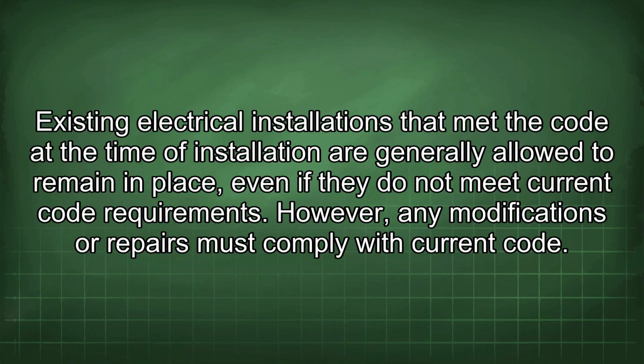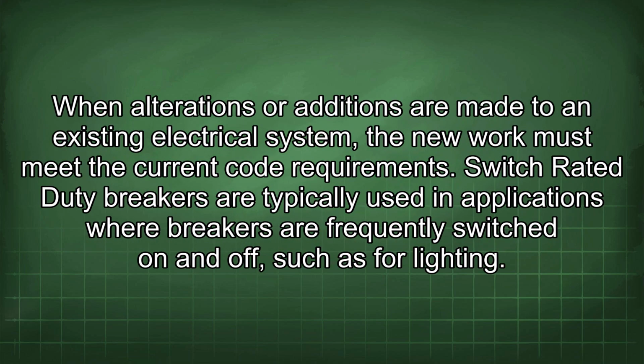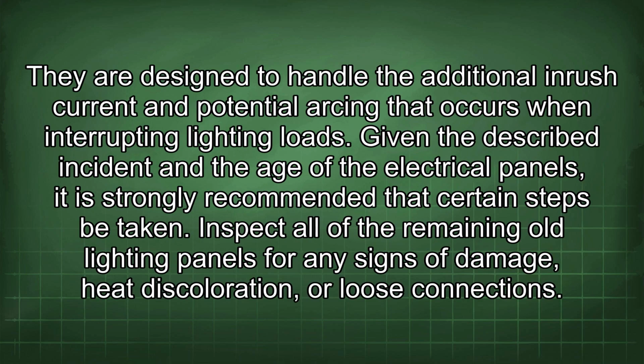Existing electrical installations that met the code at the time of installation are generally allowed to remain in place, even if they do not meet current code requirements. However, any modifications or repairs must comply with current code. When alterations or additions are made to an existing electrical system, the new work must meet the current code requirements. Switch-rated duty breakers are typically used in applications where breakers are frequently switched on and off, such as for lighting. They are designed to handle the additional inrush current and potential arcing that occurs when interrupting lighting loads. Given the described incident and the age of the electrical panels, it is strongly recommended that certain steps be taken.